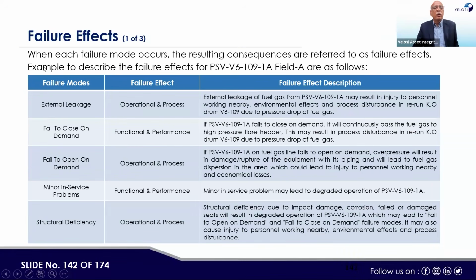Here, when there's a failure mode, there's a failure effect and a failure effect description. External leakage: operational process. Fail to close on demand: functional and performance issue. Fail to open on demand: operational and process. For example, a PSV on a fuel gas line failing to open on demand, overpressure will result in damage, rupture of the equipment with the piping, and will lead to fuel gas dispersion in the area, which could lead to injury to the personnel working nearby and economical losses. Similarly, these details are provided against each failure mode and failure effect.